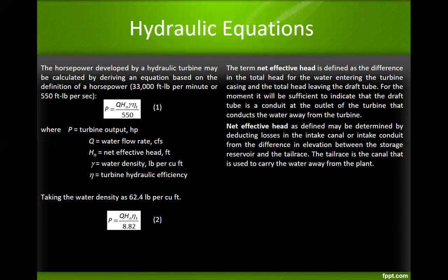Net effective head, as defined, may be determined by the deducting losses in the intake canal or intake conduit from the difference in elevation between the storage reservoir and tail race. The tail race is the canal that is used to carry the water away from the plant.